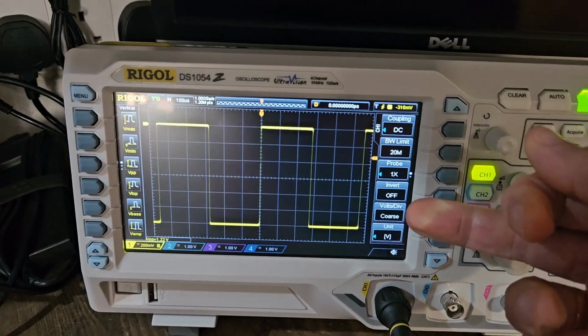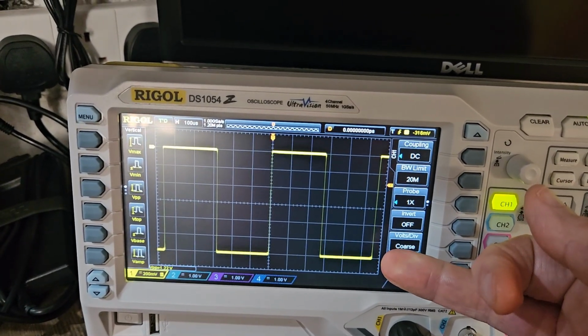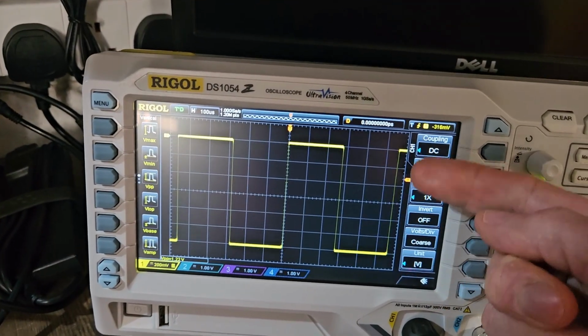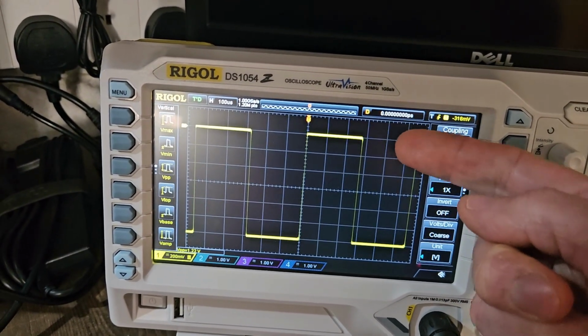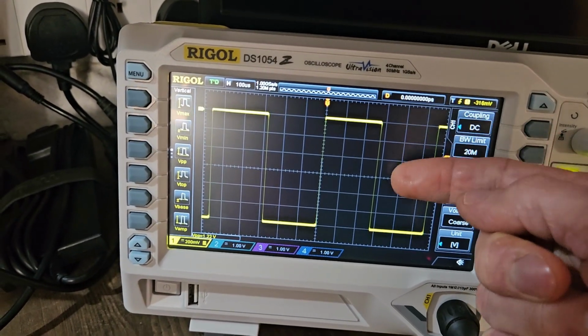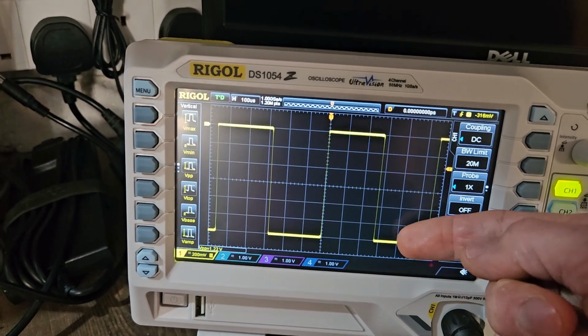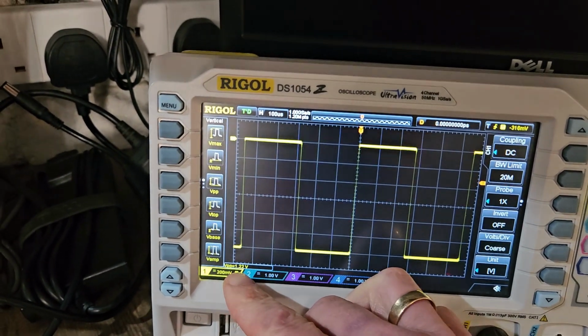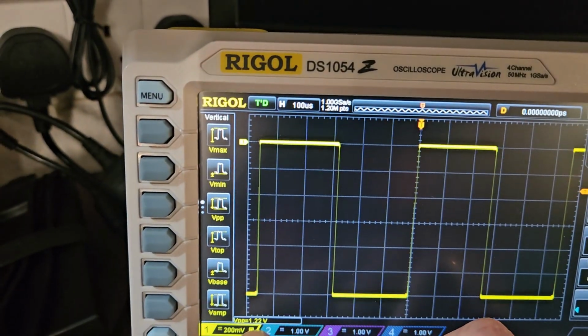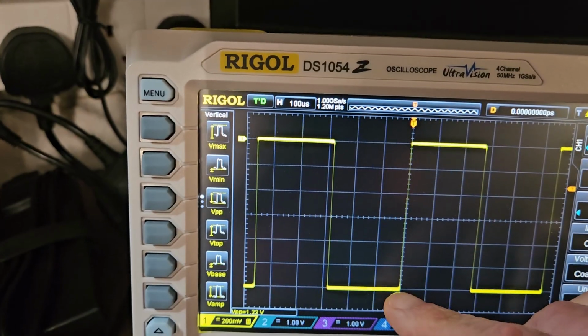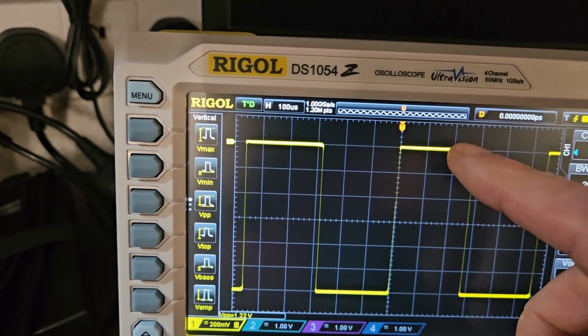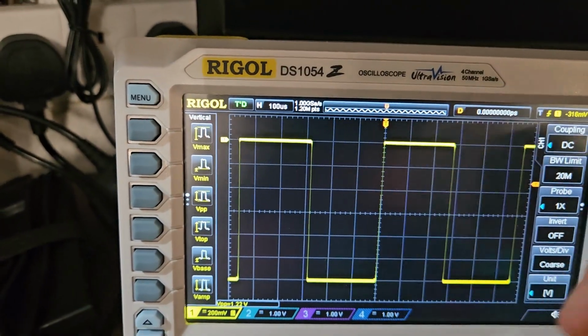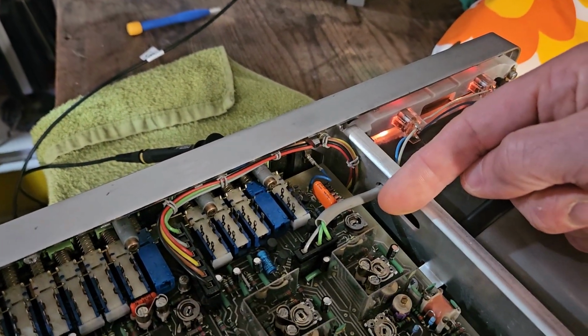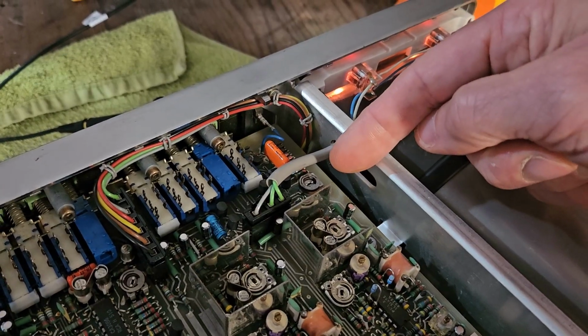So I thought I'd have a go at checking that, and with my Rigol I have just made a small adjustment to that. So now you can see it's 1.2 volts peak to peak within these divisions here, 1, 2, 3, 1, 2, 3. There's a little bit of noise there, so the actual reading here is 1.22, which it would be measuring at the top and bottom of the noise. So I've put the divisions there in the middle of the noise. I think that's probably the best thing to do. That is adjusted here by this preset, so if you need to tweak that, that's where to do it.